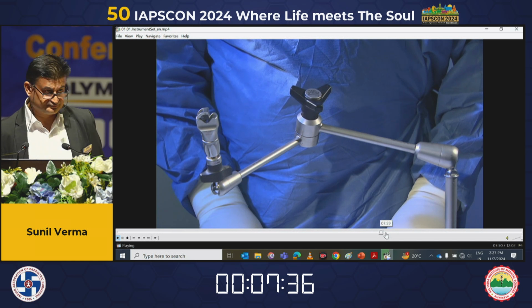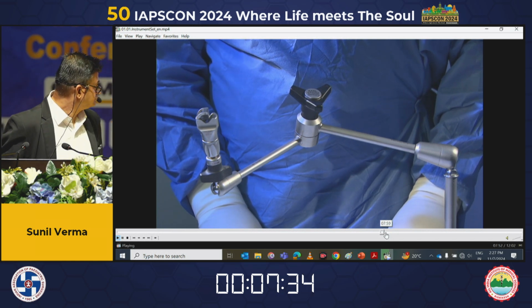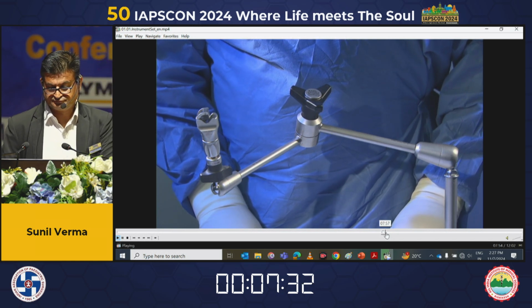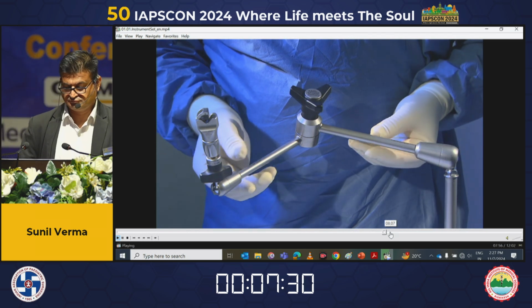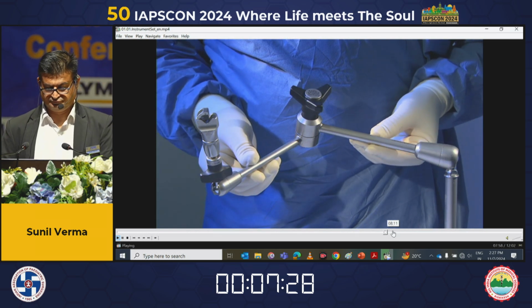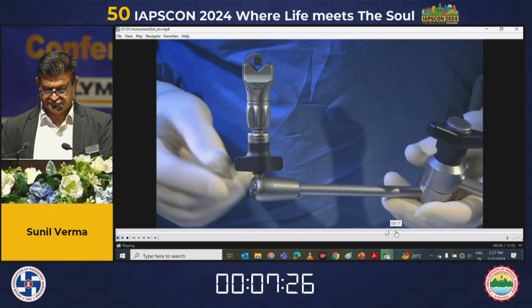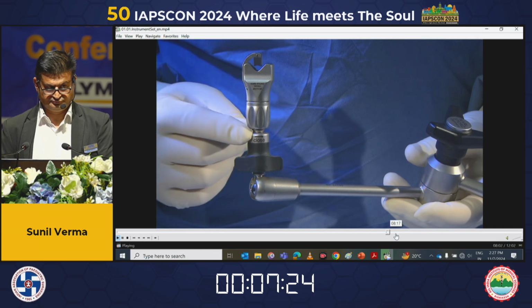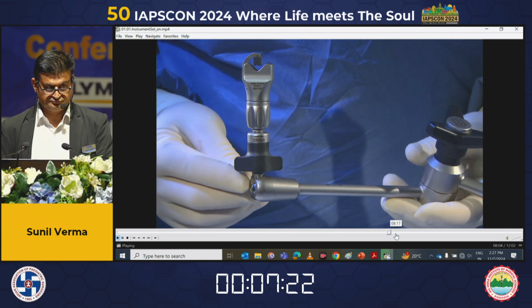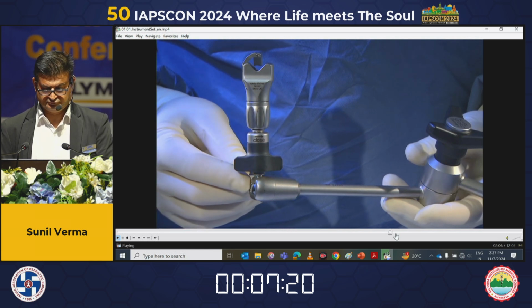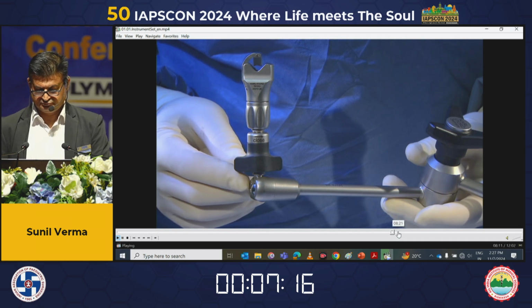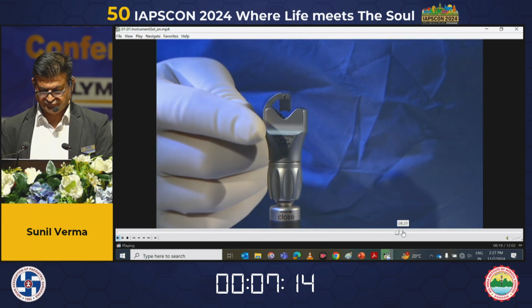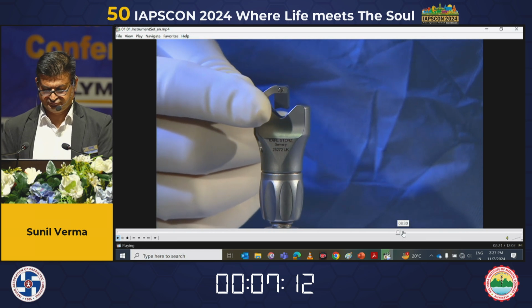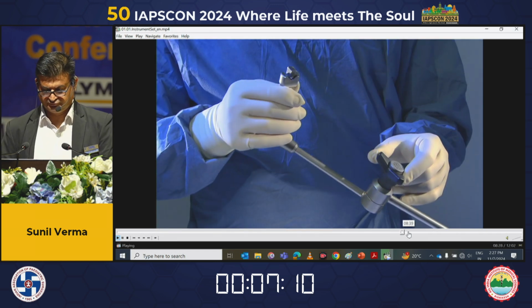Naturally, the ventriculoscope can be used freehand during the surgical procedure. However, for many indications, fixation is advantageous. For this purpose, a mechanical holding arm is available which attaches to the operating table to fix the endoscope. Using this system, the ventriculoscope can be reliably fixed with rotation stability in any position. It can be put into any desired position.